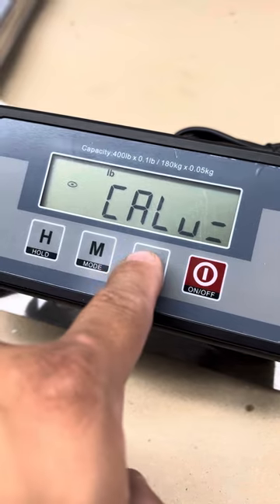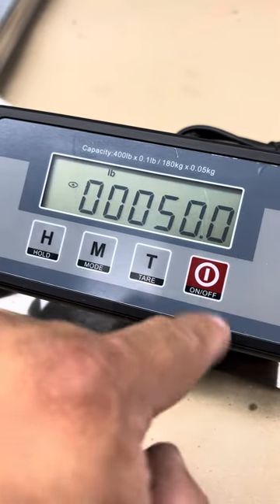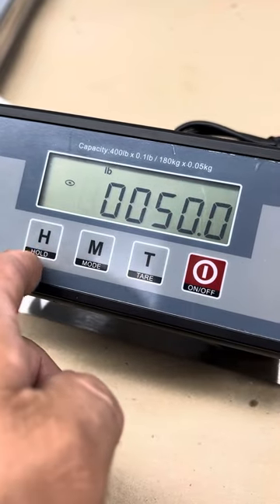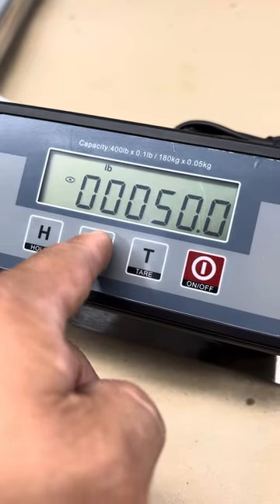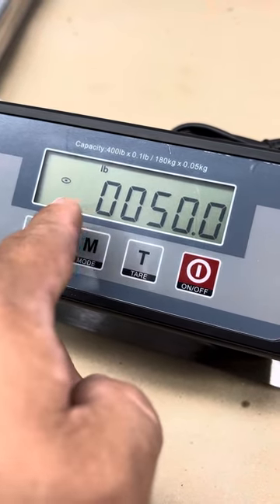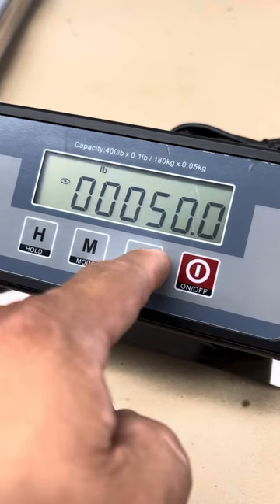How many units is that? I'm going to press tare. It asks for 50. Usually it comes up a thousand and then you change it to whatever you want. You use the mode key to move it over, and you use the hold key to increase the digit at this point.